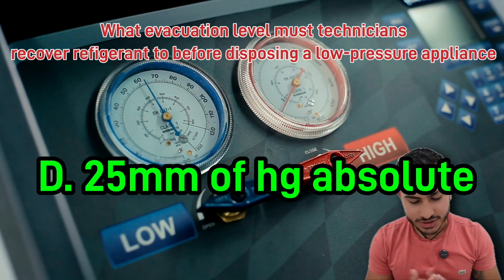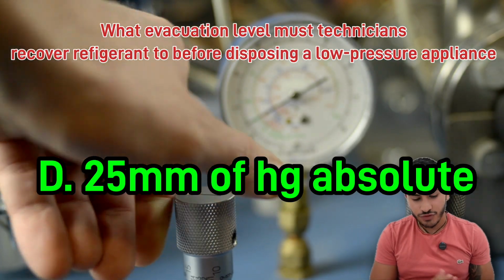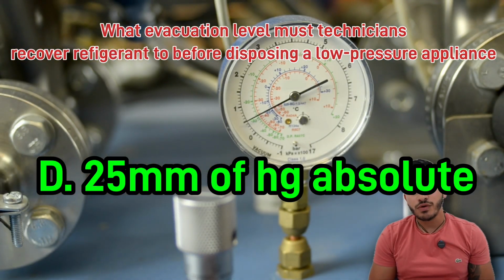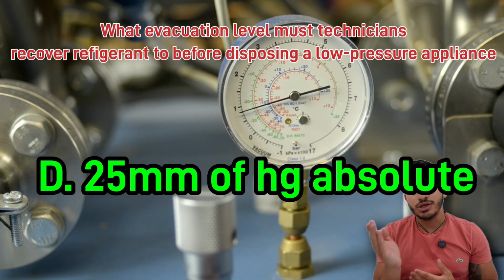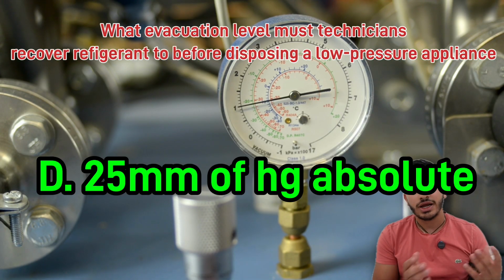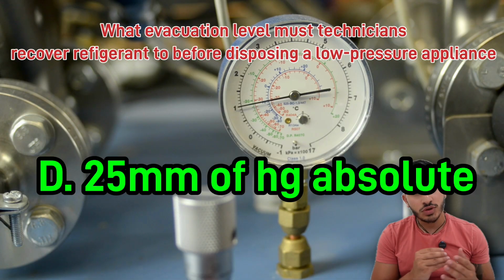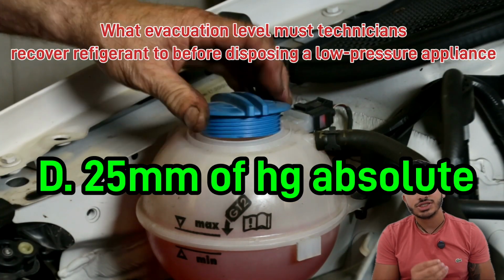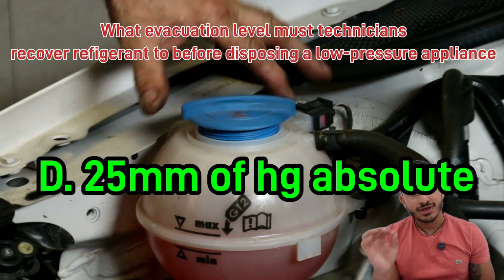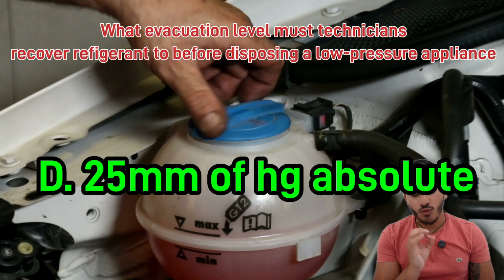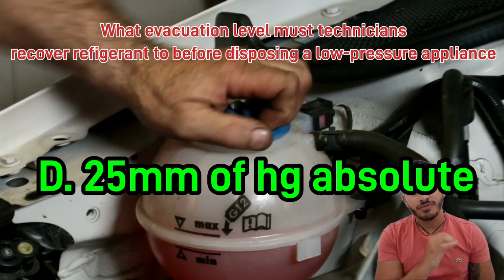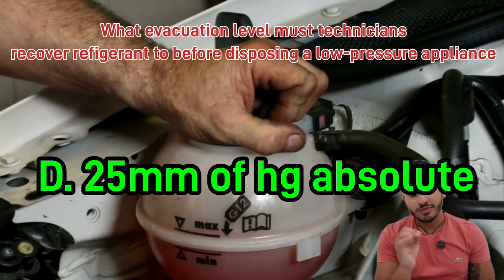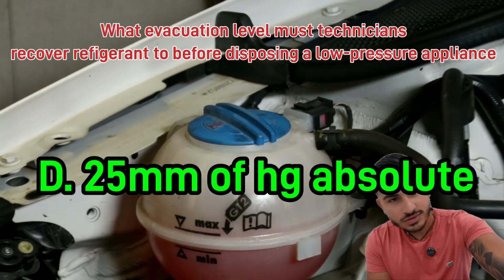What evacuation level must technicians recover refrigerant to before disposing of a low pressure appliance? It will be 25 millimeters of Hg absolute. There's one that is 25 millimeters of Hg, but this one is absolute.